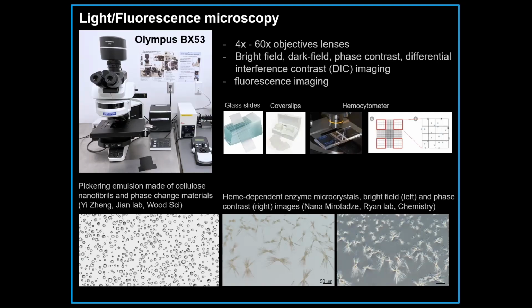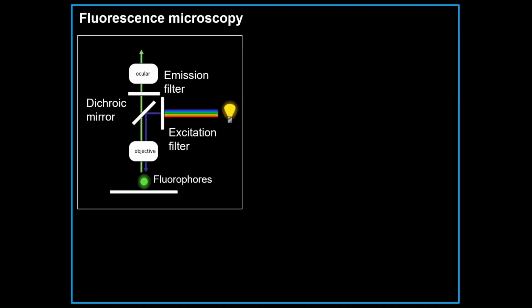clear transparent samples. And this microscope has the capability of fluorescence microscope imaging. So we use a mercury arc lamp or LED lamp as an illumination source, and the illumination light is coming from the back of the microscope. And in the middle of the microscope, it has what we call a filter cube that has an excitation filter, emission filter, and dichroic mirror. What it does is select a certain wavelength. So in this case, the excitation filter is selecting blue light, and the blue light is reflected by the dichroic mirror, traveling to the objective lens and illuminating the sample.